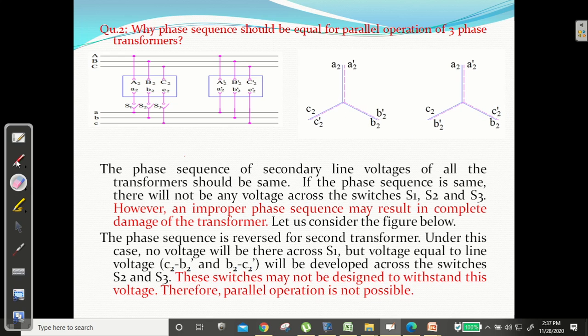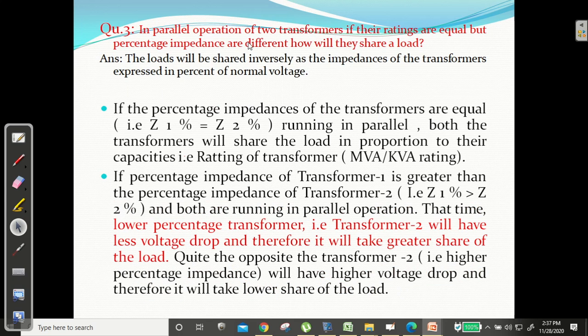Question number 3. In parallel operation of two transformers, if their ratings are equal but percentage impedance are different, how will they share a load? If percentage impedance is equal and rating is same, this means they will share equal load. If percentage impedance is same but KVA rating is different, whichever has higher KVA rating will share more, whichever has lower KVA rating will share less, no problem, but percentage impedance should be same.